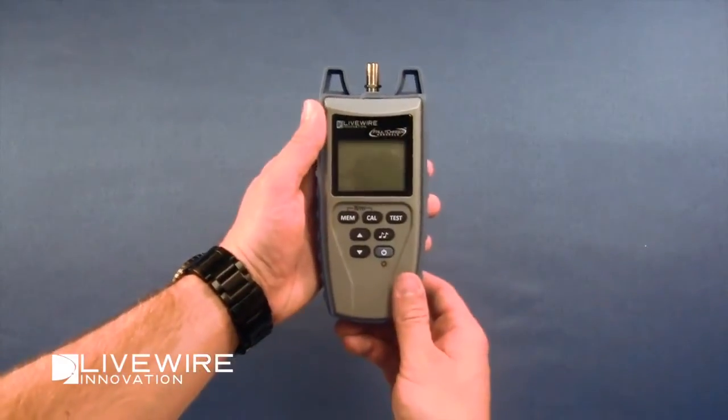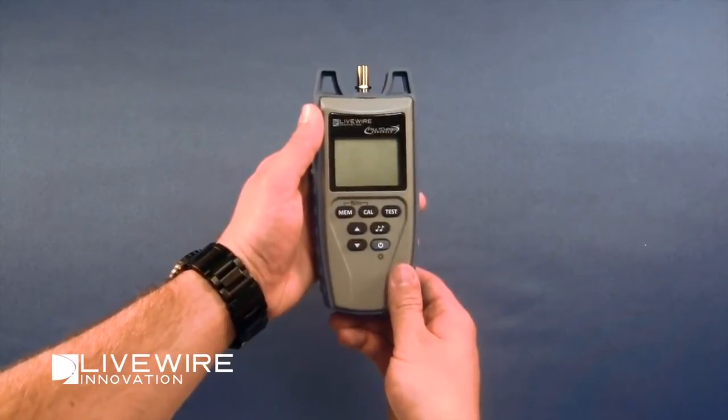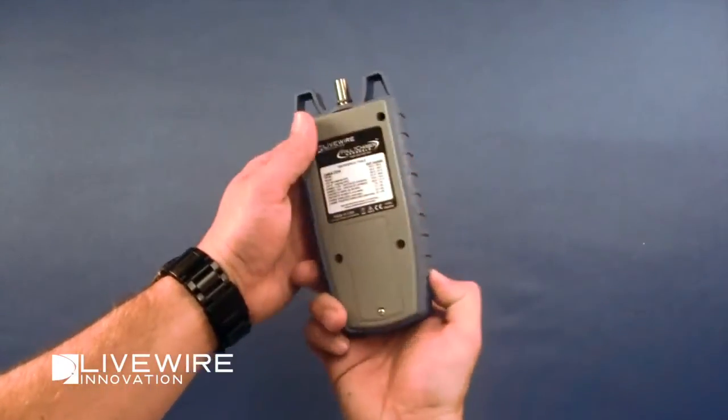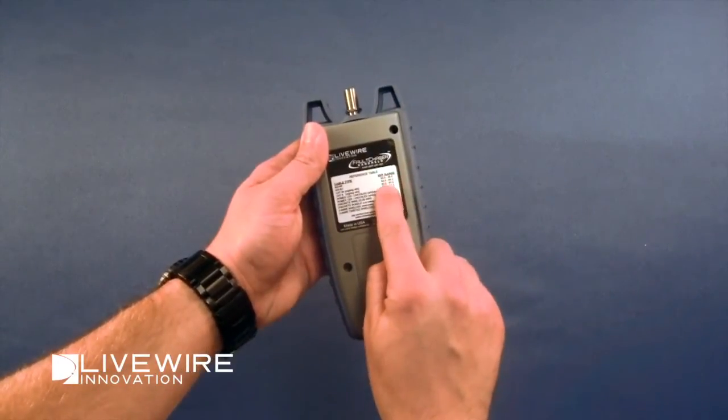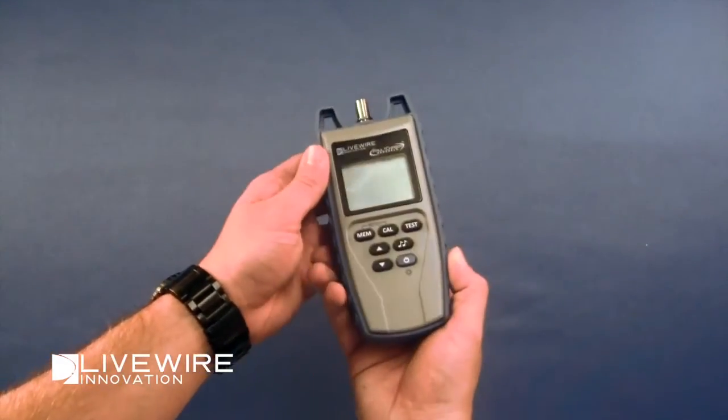To get started, we need to set the NVP value, also known as the VOP value of the cable we would like to test. Common cable NVP values can be found in a list on the back of the Fault Chaser. If the cable is not listed, we can use the calibration function which I'll tell you about a bit later.